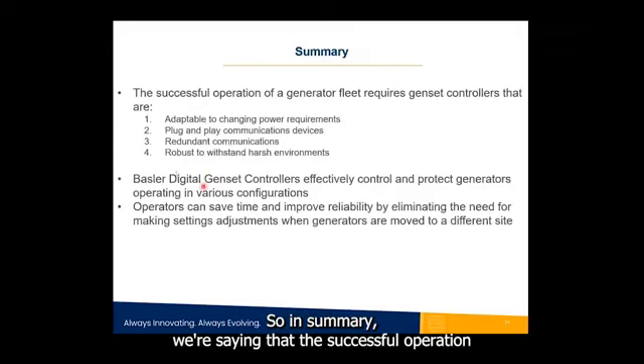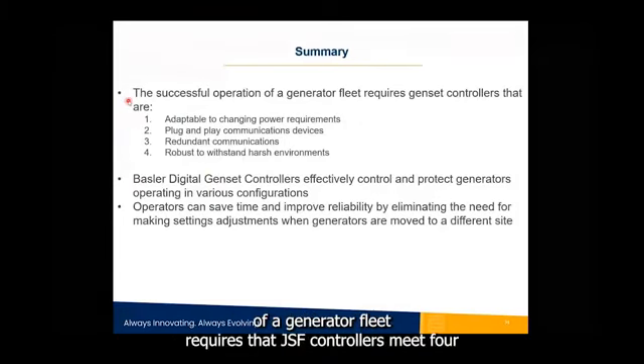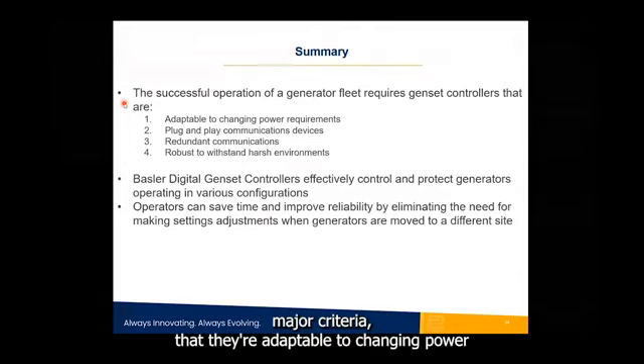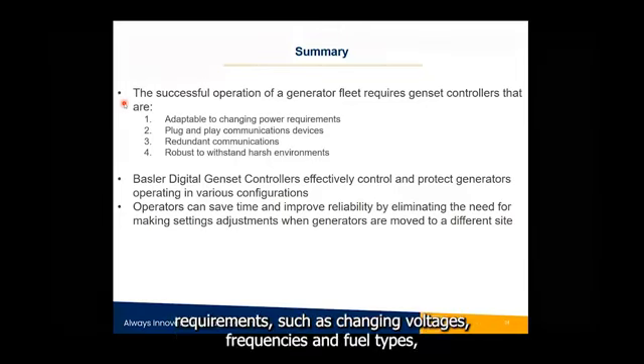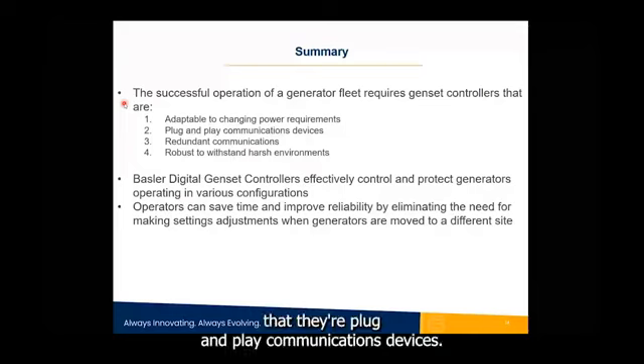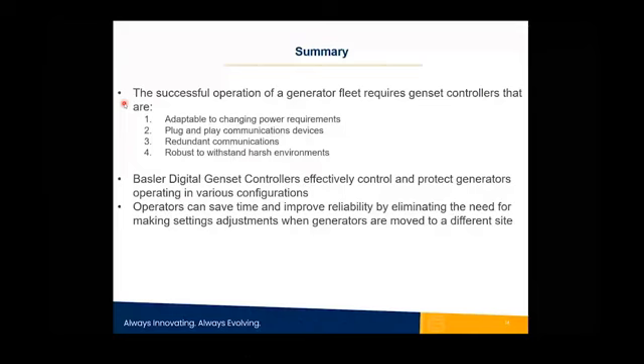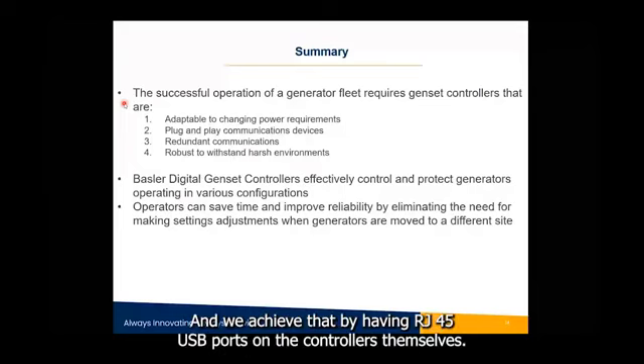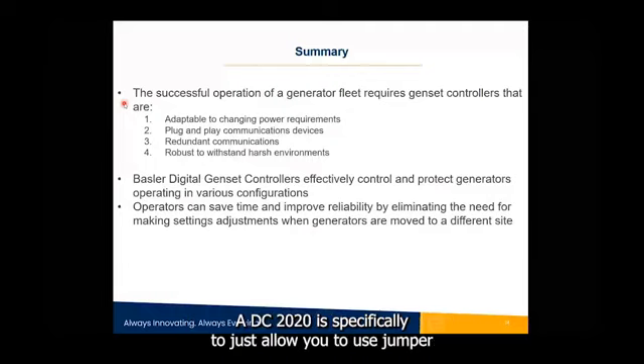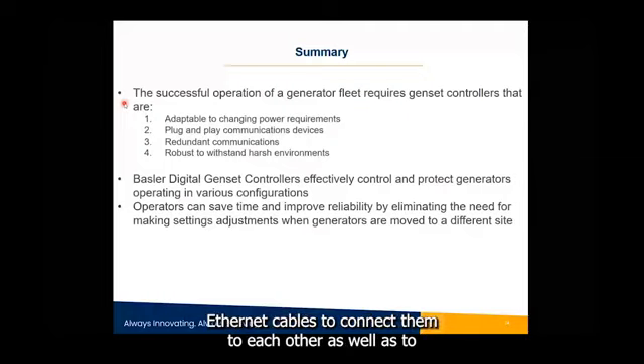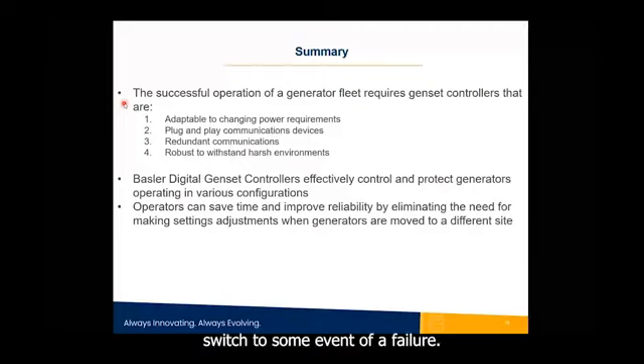So in summary, we're saying that the successful operation of a generator fleet requires that genset controllers meet 4 major criteria: that they're adaptable to changing power requirements, such as changing voltages, frequencies, and fuel types; that they're plug-and-play communications devices, and we achieve that by having RJ45 ports on the controllers themselves, the DGC 2020 HD specifically, to allow you to use jumper Ethernet cables to connect them to each other, as well as to an Ethernet switch, to add more robustness to the system in the event of a failure.